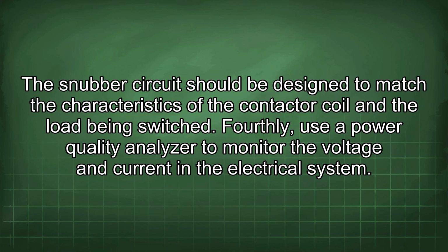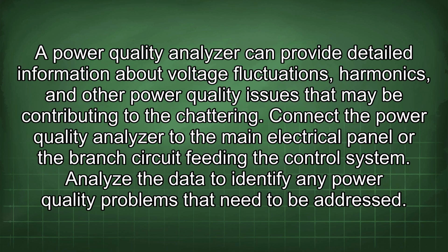Fourthly, use a power quality analyzer to monitor the voltage and current in the electrical system. A power quality analyzer can provide detailed information about voltage fluctuations, harmonics, and other power quality issues that may be contributing to the chattering. Connect the power quality analyzer to the main electrical panel or the branch circuit feeding the control system. Analyze the data to identify any power quality problems that need to be addressed.